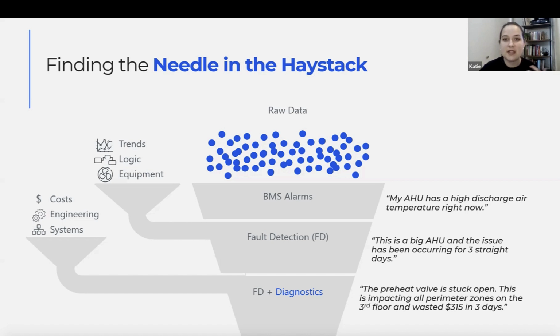The last little D there, so when we say FDD, we're talking about fault detection and diagnostics. That last little D there is really the big important piece. And that assigns a cost to the problem. It does some engineering, and it also knows what other systems might be impacted by that. So the example here, one more level of detail, would be the preheat valve is stuck open. So I actually know it's the preheat valve because I know my logic, I have some engineering, I know what type of equipment I have, and it's impacting the perimeter zones only on the 3rd floor, and it wasted $315 in 3 days. So it's really taking that extra bit of information, giving your technician even more information at their fingertips to decide whether they need to act. And then when they act, they know what to do without spending a lot of time doing the research.